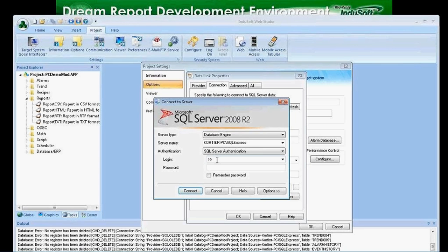And good thing to note: when you configure this database, when you install this database, you cannot be logged on as a user with administrative privileges. You have to be logged on to the computer as the administrator. So that's very important. I've proven to myself that it won't work if you try it and think, oh, I can make this work. No, it's actually a Microsoft requirement, because of the way the data source names are created. You have to be the administrator, not logged on with administrative rights.